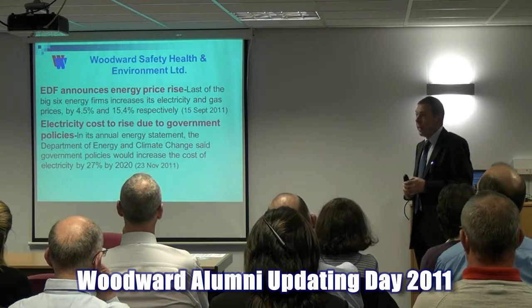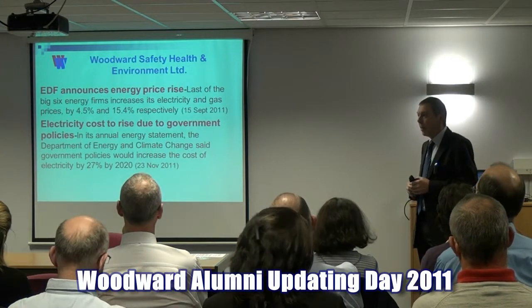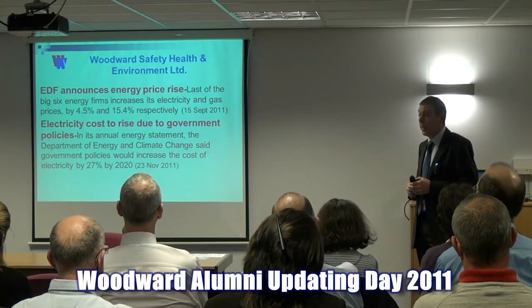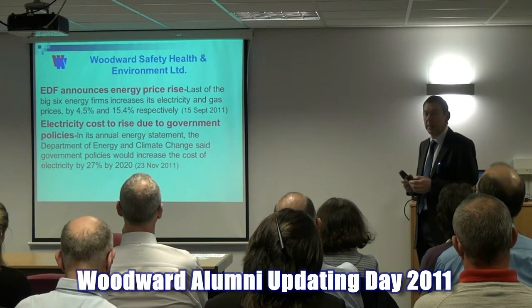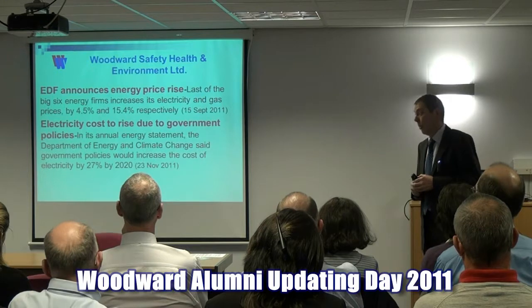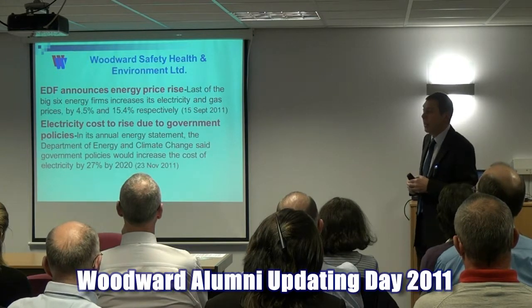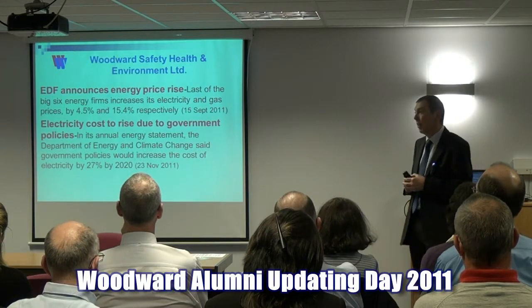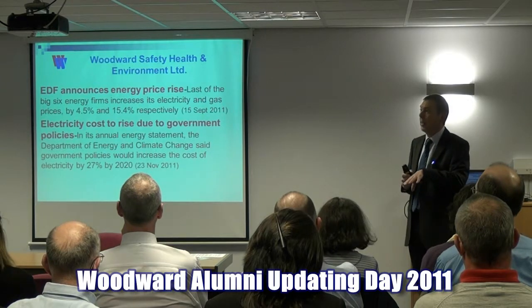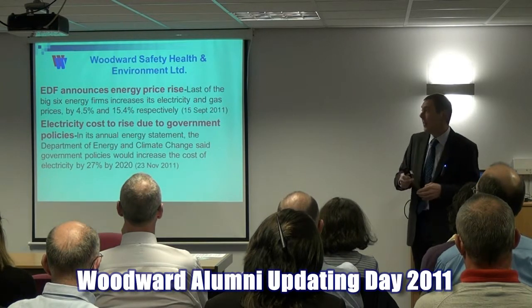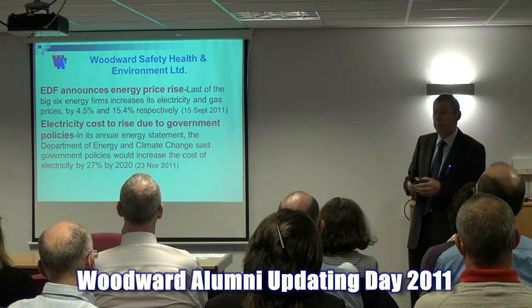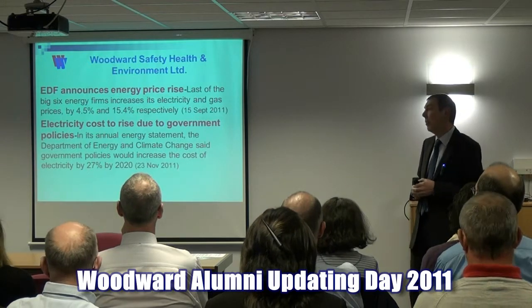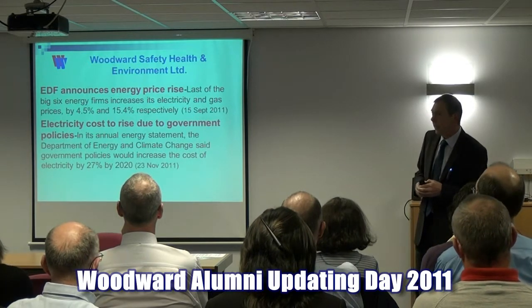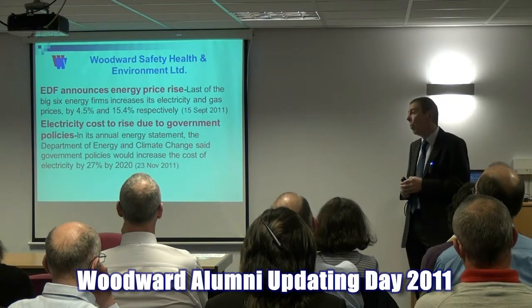The electricity suppliers do a rather ruthless test. The city had been underwater, and clearly all the cables were adversely affected - water would possibly be in them. Some areas of Carlisle didn't get mains electricity back on in a stable fashion until the Monday evening. Some didn't get it till much later in the week because certain cables had been damaged and needed replacing. There are several things you can do with a damaged cable if it's had water in it.